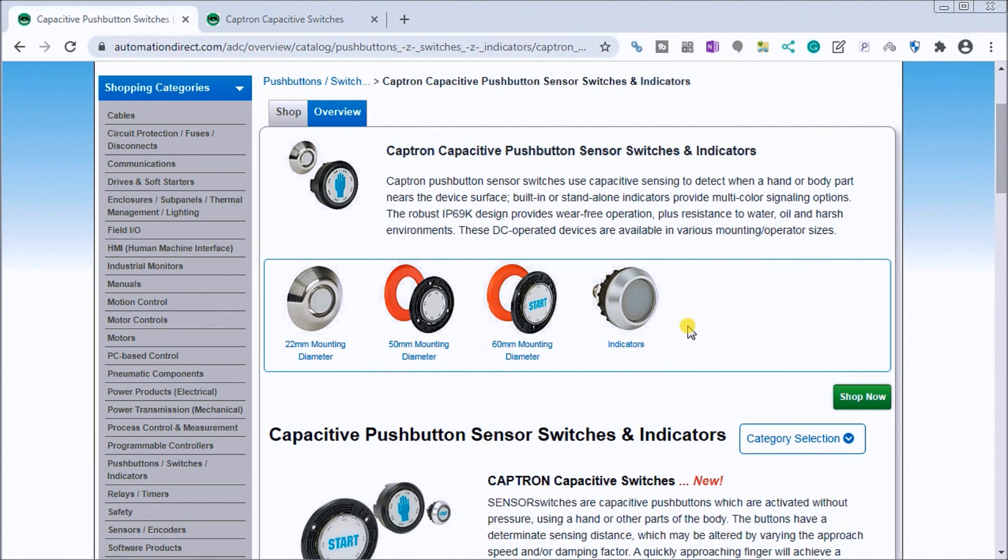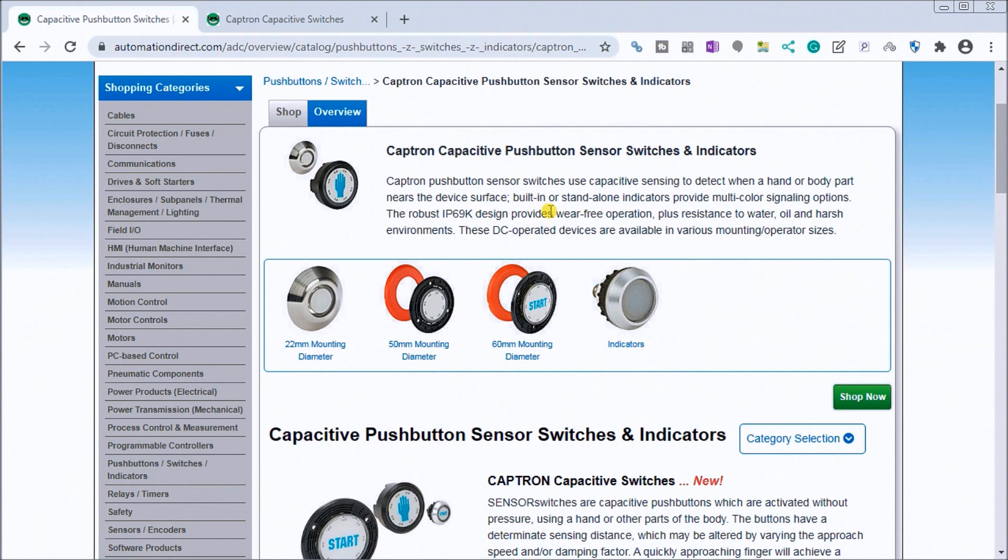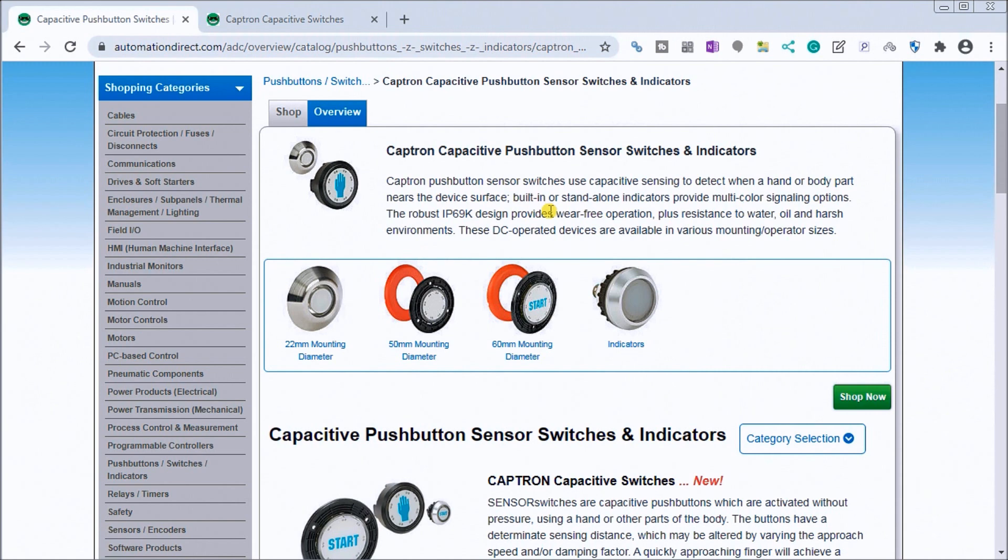So a capacitive switch - normally pushbuttons on a panel are a mechanical device and it becomes sticky when you get too much dirt or oil that's present. Now capacitive pushbuttons don't have any moving parts at all, so the life expectancy is increased. And things like disinfectant sprays can be applied directly to a capacitive pushbutton and left to dry, so it becomes more effective and this is better for the safety of your operator.